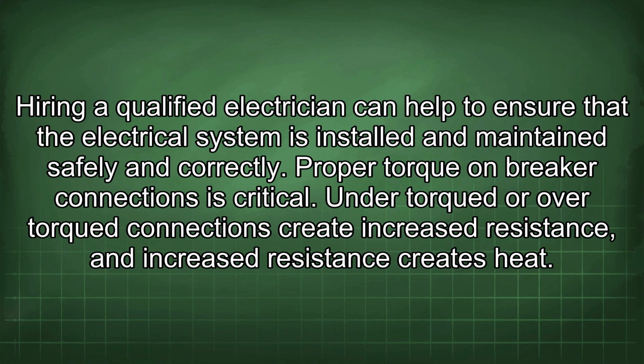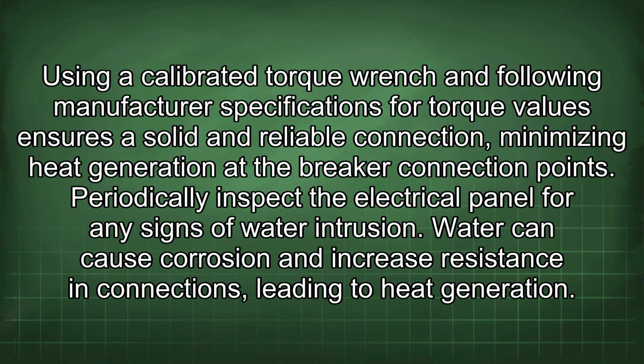Proper torque on breaker connections is critical. Under-torqued or over-torqued connections create increased resistance, and increased resistance creates heat. Using a calibrated torque wrench and following manufacturer specifications for torque values ensures a solid and reliable connection, minimizing heat generation at the breaker connection points.